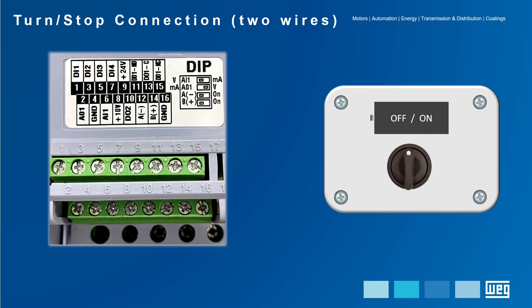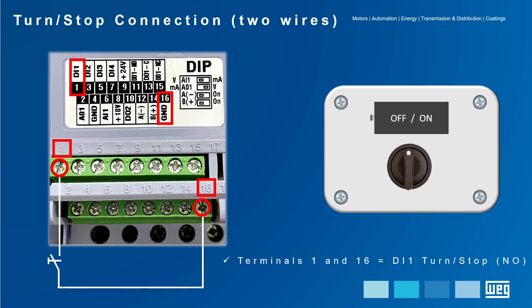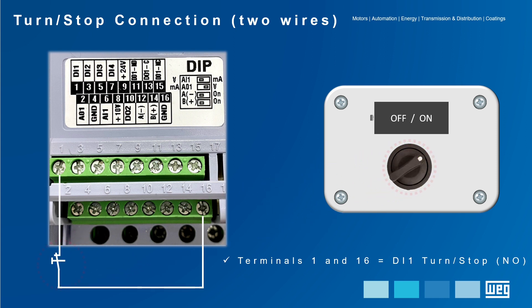By identifying the terminals of the respective digital input which will be used for this function, in this example we will use digital input DI1, connecting to terminals 1 and 16 to connect the normally open contact. This means when switching, it will close its normally open contact, transmitting a signal to digital input DI1.